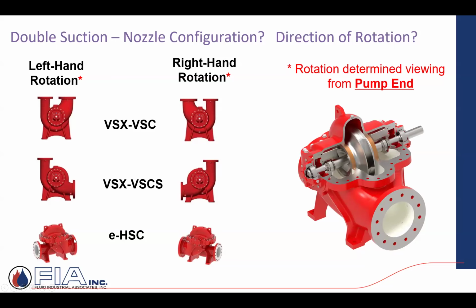And then other times, just from maybe an existing installation, I might have this, what they call a horizontal split case. And it's horizontal suction, horizontal discharge. So you have these different configurations. You just want to be aware. But the whole family is double suction. And you're getting into much higher flow rates. The load is too great to put it on that one end. Evenly load the impeller and the shaft and the seals.